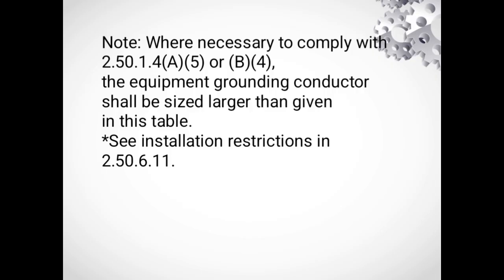Pipes and frames. Metal water pipes and building frames need to be connected, bonded, to the electrical grounding system. Lightning rod systems must connect to the building grounding. Multiple raceways. If conductors are installed in parallel in multiple raceways, a wire type equipment grounding conductor, where used, shall be installed in parallel in each raceway. The equipment grounding conductor installed in each raceway shall be sized in compliance with 2.50.6.13 based on the overcurrent protective device for the feeder or branch circuit. Metal raceways or auxiliary gutters in accordance with 2.50.6.9, or cable trays complying with 3.92.2.51 B, shall be permitted as the equipment grounding conductor.